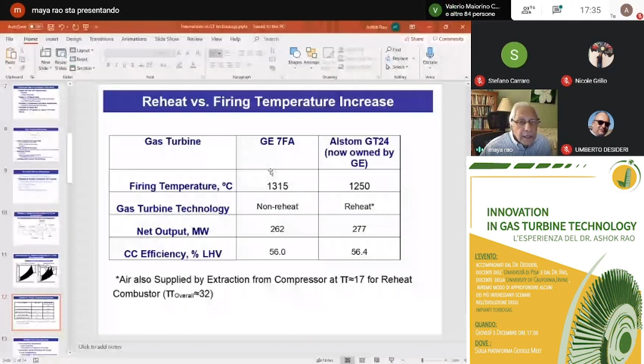Now, an additional advantage of the reheat cycle is not only reducing the firing temperatures, not having to have very high firing temperatures, but also the destruction of NOx. This is actually measured with the GT24 that I showed the performance for previously. What they found is the NOx that forms in the HP combustor was actually being destroyed, a portion of it, in the reheat combustor. So on a net basis, you get lower NOx emissions because of the reheat cycle.